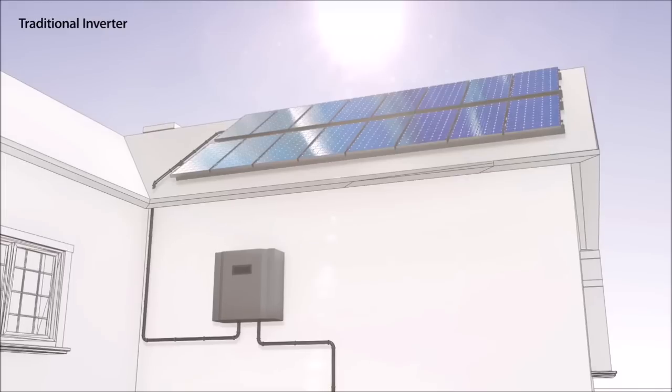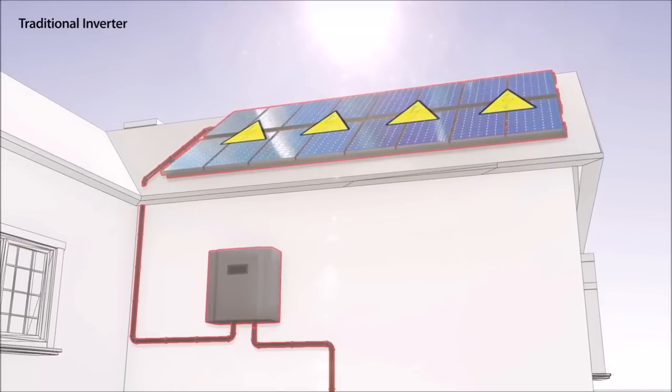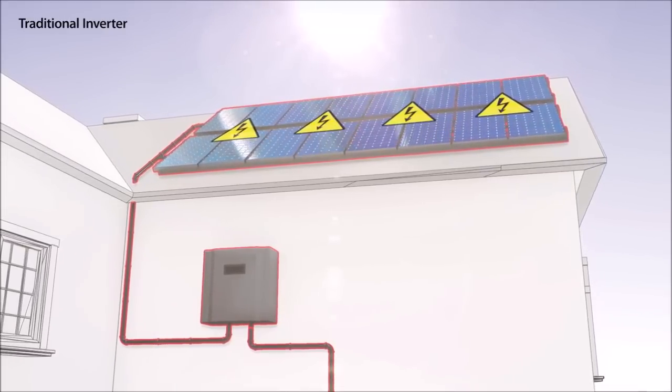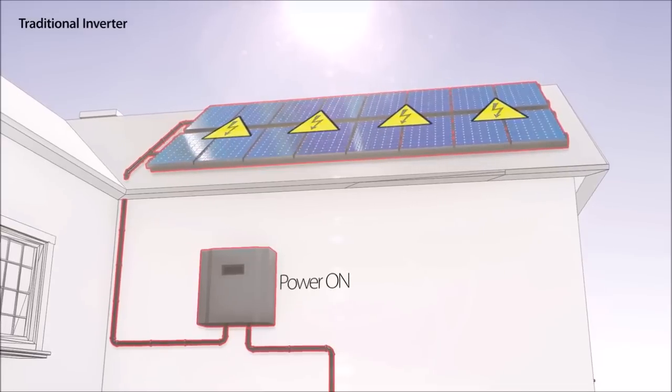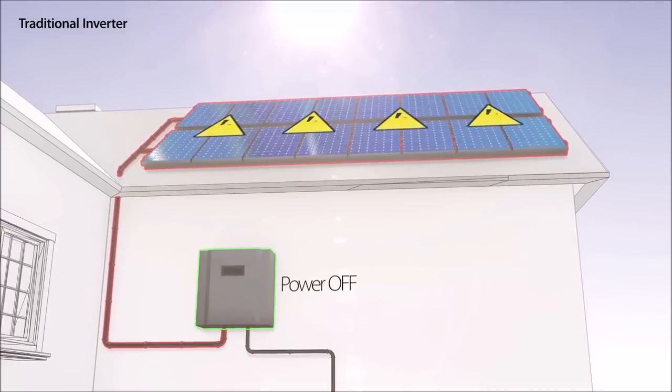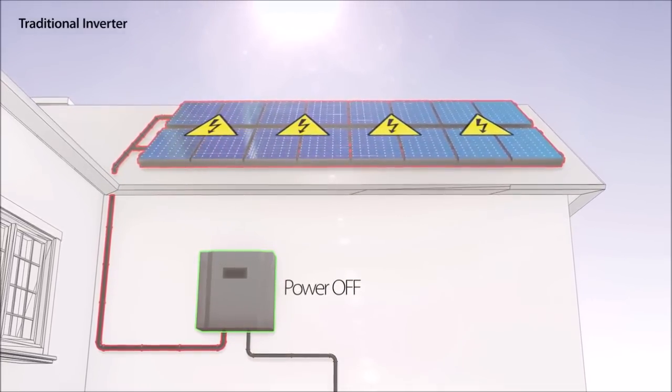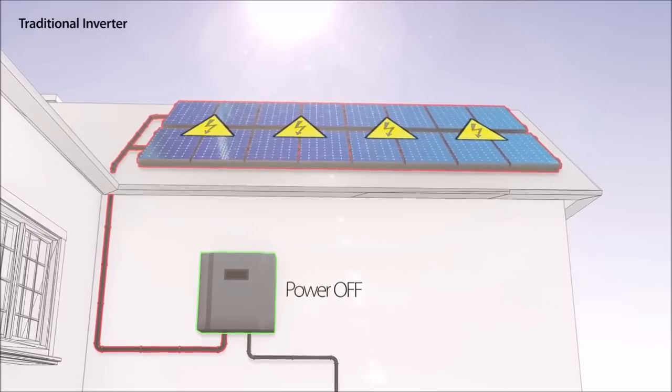The DC cables, which connect the panels to a string, carry high voltage as long as the sun is shining. The traditional inverter cannot shut down the panel's DC voltage and therefore poses serious risks to installers and firefighters.